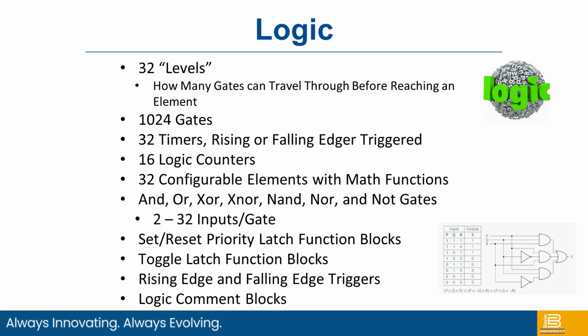1,024 gates that are available, 32 timers, and we can do it both on a rising or falling edge triggered, 16 logic counters, 32 programmable elements with math functions. There's AND, OR, exclusive NOR, and other gates. And you can have 2 to 32 inputs per gate.